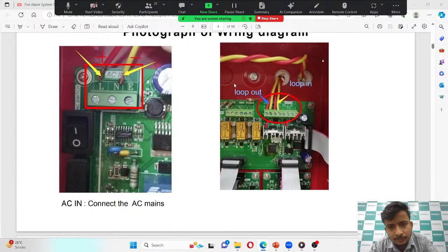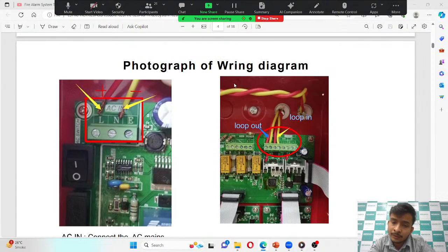Sir, another question: after 20 to 30 devices, we need to connect an isolator module for this. Means you don't have any inbuilt isolator for devices? We have detectors with inbuilt isolator also. We have both types of detector, with inbuilt isolator and without isolator. For without isolator, you need to install the isolator module, but with isolator you do not need to install the isolator module.